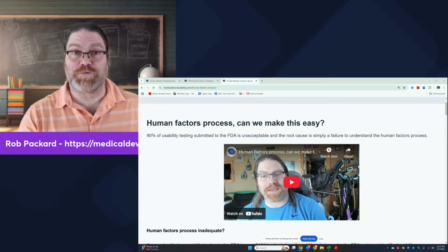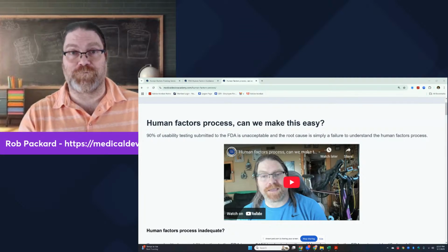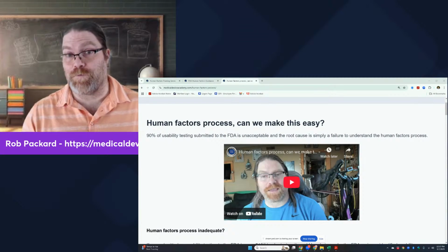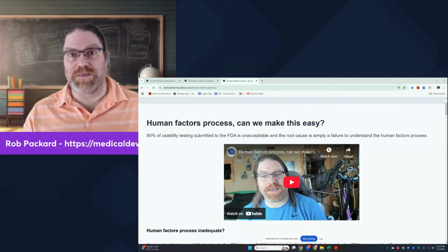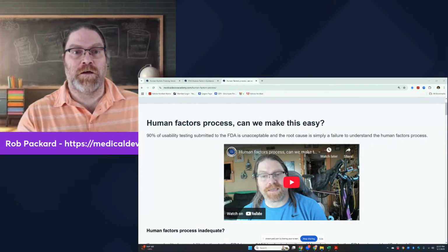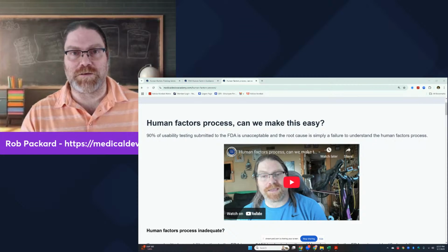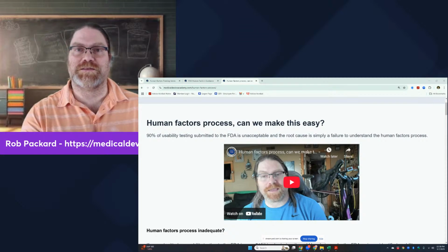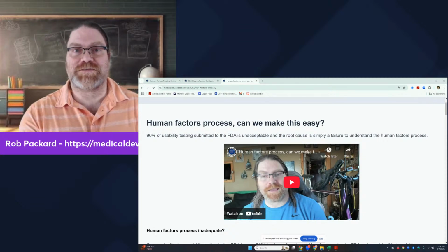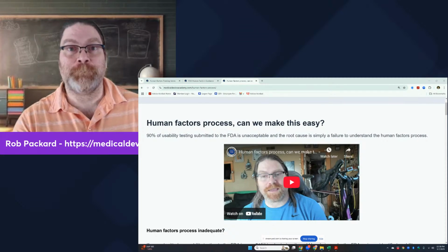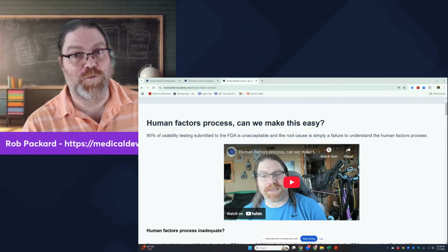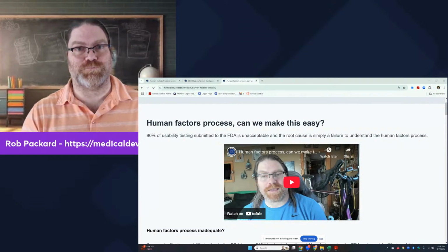You also have other types of risks, not just use errors, but you also have software errors, bugs. There's a whole list of them, 6 pages in a table listing typical hazards associated with software. That's in a standard. You have all those questions I talked about in the 24971 guidance document about risks. You have to do those as your identification of risks and hazards and hazardous situations. At the second phase, these are the inputs from risk management activities, the risk management process. That's where that stuff comes in. It's the hazard identification process.